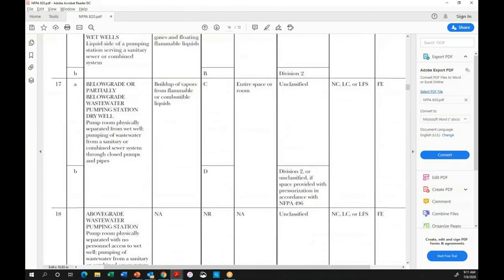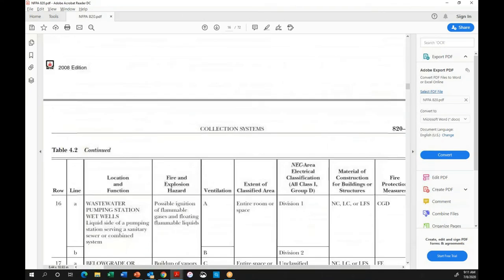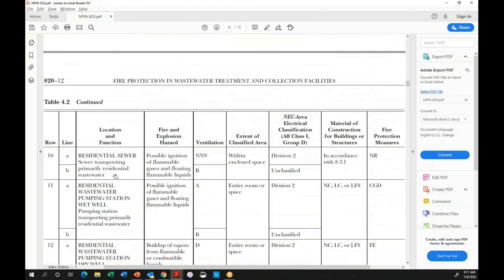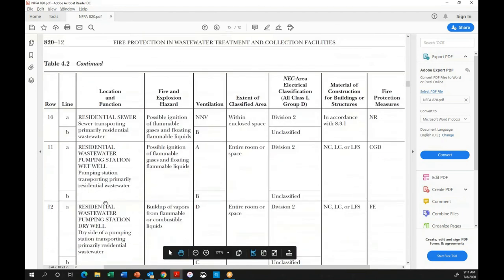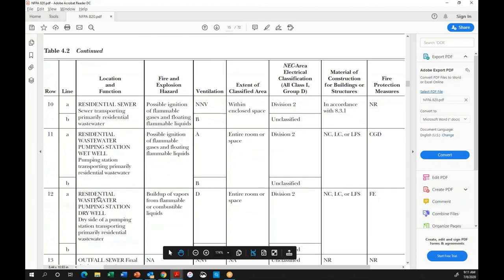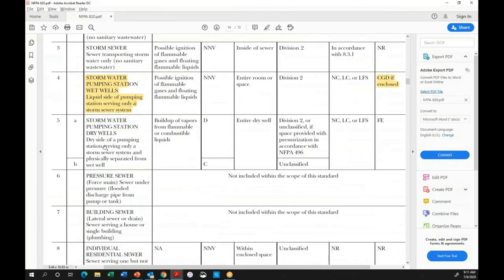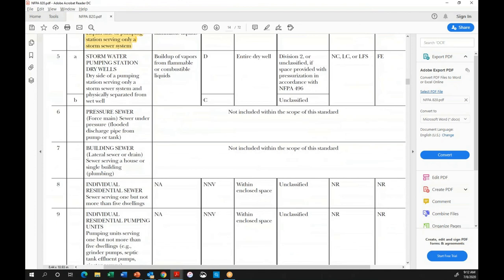If I can find where we're at, chapter 4.2, this should be the section here. Residential wastewater pumping station dry well. So here's a wet well, pumping station wet well. It's showing as a Div 2. Yeah, stormwater pumping station, stormwater. These are all most likely Div 2 because you're going to have the presence of methane, maybe not all the time, but there is a risk of that. So it would be Div 2. If it were Div 1, it would mean you have an explosive gas present all the time.